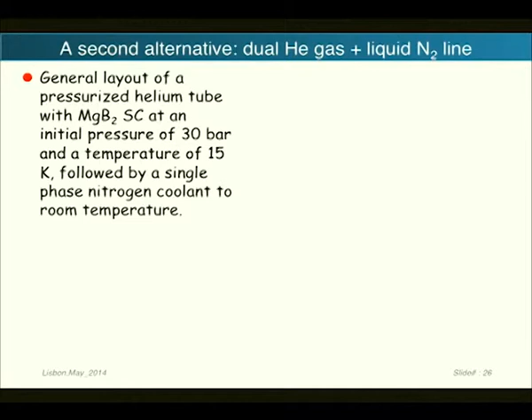The second alternative is the dual helium gas and liquid nitrogen line, which is represented here. It starts with an initial pressure of 30 bar, running at 15 Kelvin. And this is the part with helium gas. You have the same system here, helium gas, and that is surrounded by a nitrogen system, which works between that temperature and the room outside. So it's a dual system: nitrogen input, nitrogen return, helium input, and helium out. Helium is gas in this particular case.